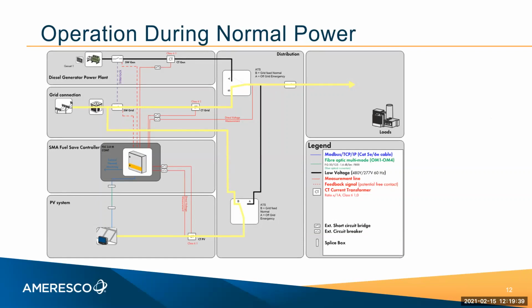In this case, the PV is connected and runs up through and connected between the transformer and the building loads. We don't show metering on here, but the metering would be between the ATS on the bottom of the distribution section and the grid connection up on the top left. So 100% of the PV is run through a front of the meter utility meter. Then 100% of those credits are applied to the account that's associated with the loads themselves. So in the grid connection box, second from the top on the left, that's coming in from the utility.